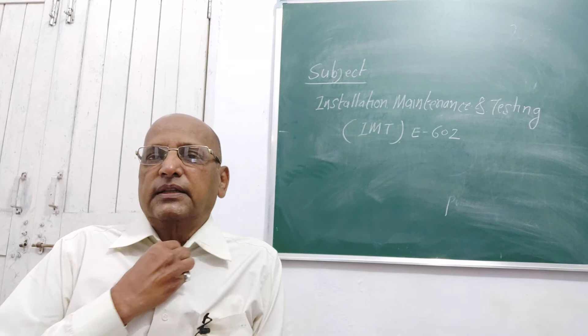Then apart from these accessories, a sleeper is required. A sleeper is made of wooden strips of thickness about 10 inches and size about 3 feet by 1 feet. For supporting the equipment on the base or ground, we put the sleeper, and with its help we can shift this equipment onto the plinth using the chain pulley block or cranes. These are the accessories for heavy equipment.